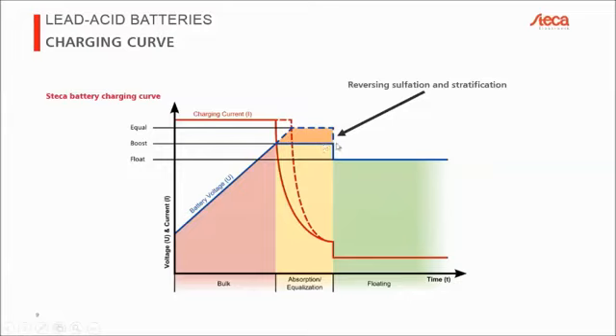Well, there's a couple of reasons. First of all, it's to reverse the two effects that we had before, the sulfation and the stratification. Remember, the sulfation was the crystals building up on the lead plates, and the stratification is the water and the acid coming apart and building layers inside the battery. So when we have higher voltages, in the boost or the equalization phase, we have a controlled gassing of the battery.